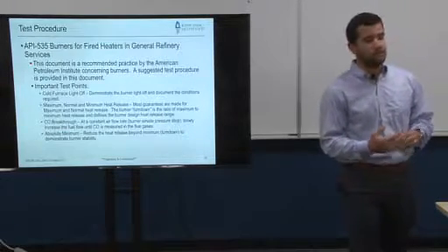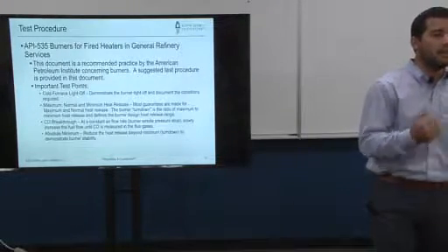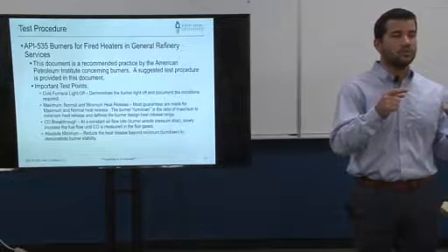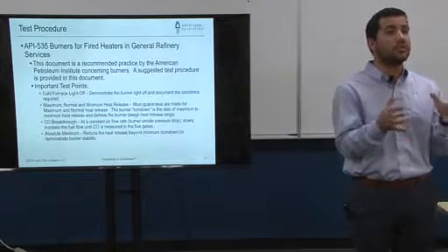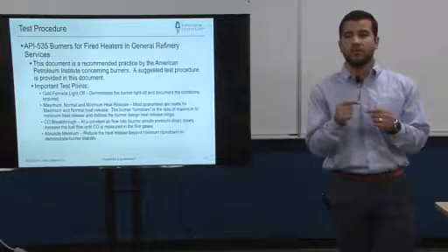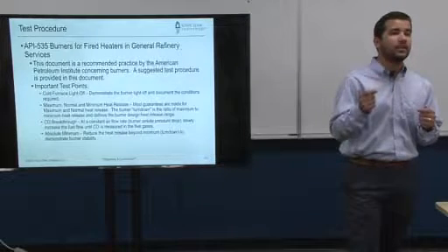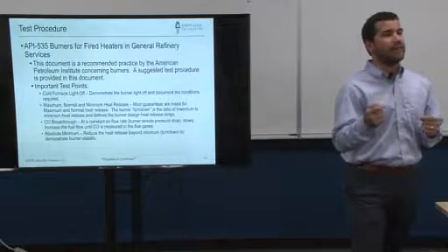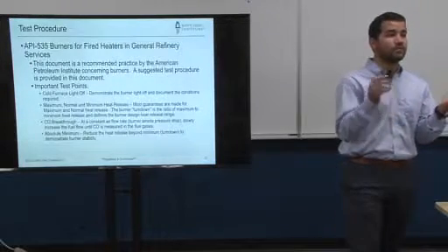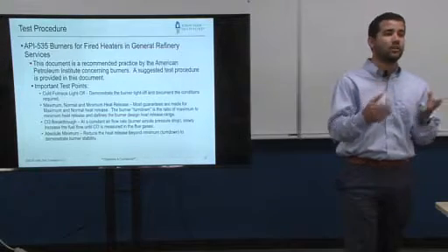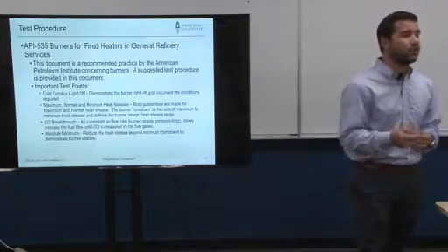What a CO break is: imagine you're operating your burner in your furnace, and as you introduce fuel, there's going to be a point at which you can no longer entrain any more air through the burner because you are geometrically limited. If you keep increasing the fuel, the excess oxygen inside the box is going to get closer and closer to zero. CO break is the point when you get past that, where you will not have enough air to combust the fuel you're putting into the furnace, and now carbon monoxide, or uncombustibles, will form. So that's what they call a CO break.